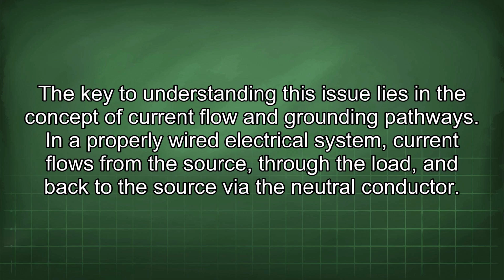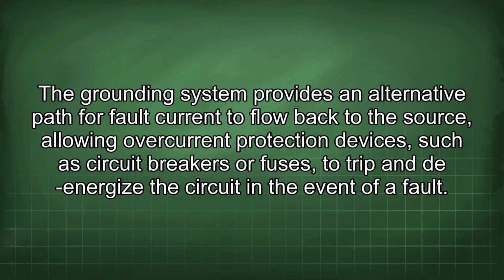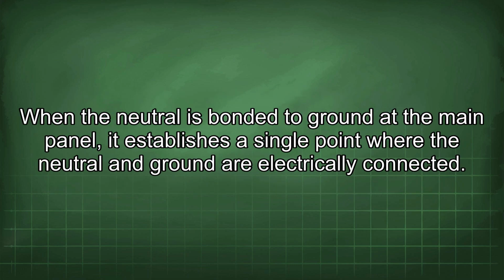In a properly wired electrical system, current flows from the source through the load and back to the source via the neutral conductor. The grounding system provides an alternative path for fault current to flow back to the source, allowing overcurrent protection devices such as circuit breakers or fuses to trip and de-energize the circuit in the event of a fault. When the neutral is bonded to ground at the main panel, it establishes a single point where the neutral and ground are electrically connected.